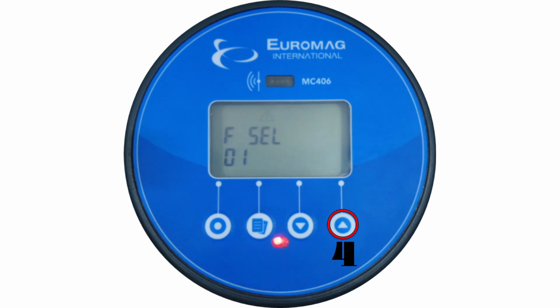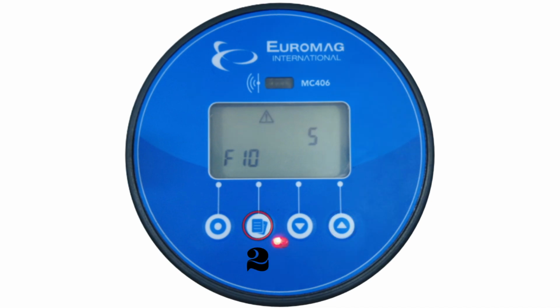Go ahead and enter the function menu. Press the number 4 button to navigate to function 10, then press the number 2 button to access function 10. Function 10 is the sample's measurement frequency. With a value set to 5, this converter will take a sample every 5 seconds and average this value by the damping value we will set in function number 12. Please note a value less than 15 will shorten the battery life of the converter.